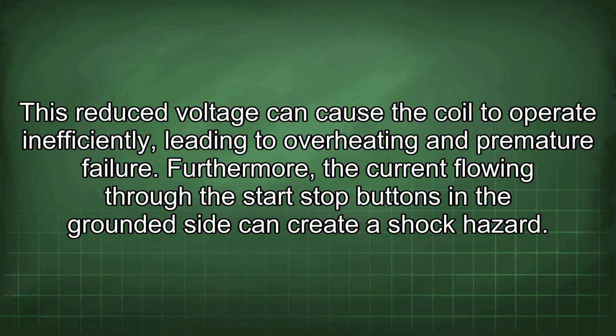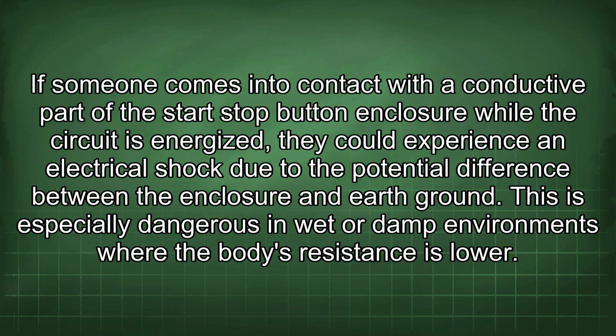Furthermore, the current flowing through the start-stop buttons in the grounded side can create a shock hazard. If someone comes into contact with a conductive part of the start-stop button enclosure while the circuit is energized, they could experience an electrical shock due to the potential difference between the enclosure and earth ground. This is especially dangerous in wet or damp environments where the body's resistance is lower.